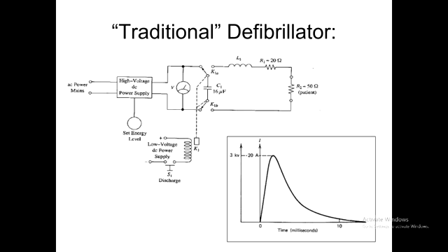The only way to do that is to have two batteries, one that's perpetually on charge and the other one that's being deliberately discharged, because there are certain batteries that need to be cycled in order to work. That means the weight doubles, which means its usefulness as a crash cart type scenario is difficult. So there are logistics problems with whatever you do in this arrangement.